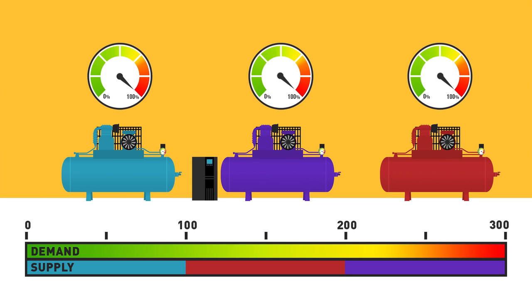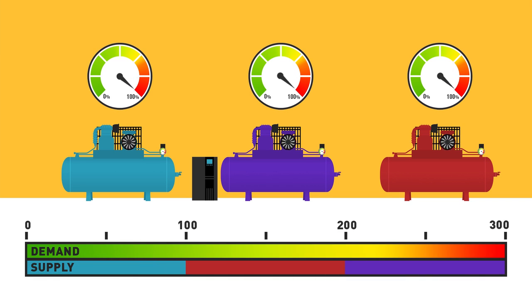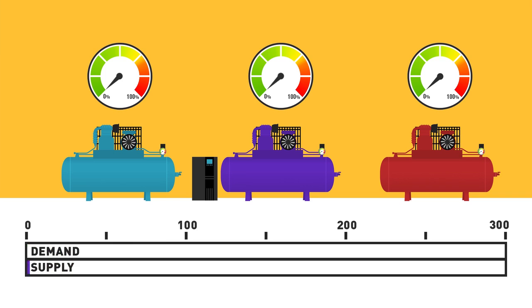Installing a VFD on one compressor allows you to step it up incrementally from zero to three full compressors. Starting with the VFD trim compressor, we can go from zero to one in small increments, using only what we need.